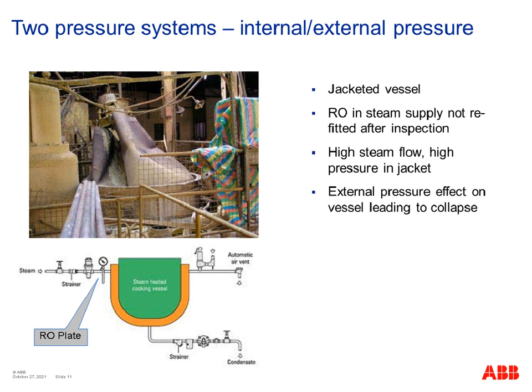So, first case study here. This is an example of why you need to consider the two sides of a heat exchanger system to be separate. Here we have a steam heated vessel with a jacket, and steam going into the jacket to keep the temperature up in the vessel in normal operation. And we have steam going into the jacket via a restriction orifice plate, condensing in the jacket and leaving as a liquid, as condensate. There's also a vapor outlet line to a relief valve, which is shown on the right-hand side of the schematic, and an automatic air vent there as well.